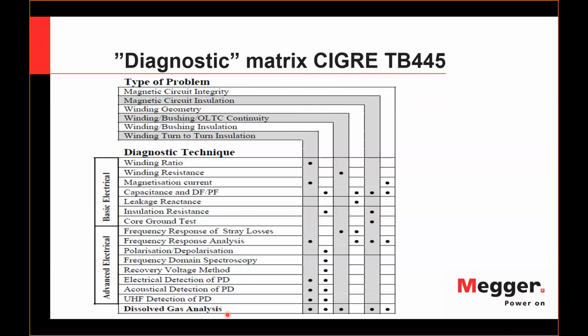At the very bottom, there is a very informational and powerful method where you take a sample of your insulating fluid from the tank and send it for chemical analysis to check the dissolved gases. It can help you find a lot of problems already, but it definitely does not cover all. So if your attention was triggered by suspicious DGA results, you can schedule an outage of this transformer and plan some tests.